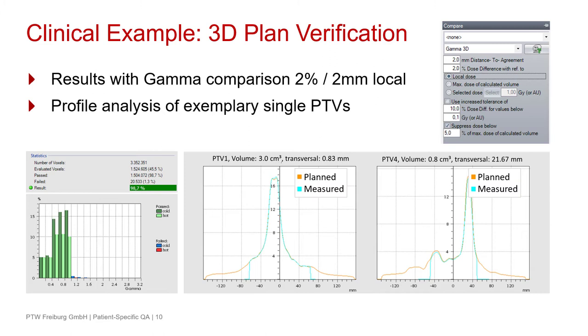I also want to mention that with VeriSoft you have many useful tools for your gamma analysis that each user can choose for themselves. For example, you can decide whether you want a two-dimensional or three-dimensional gamma analysis, local or global criteria, and you can also activate second and third pass criteria. Each physicist can decide which is the best evaluation criterion for their application.